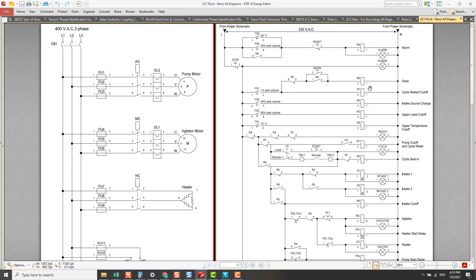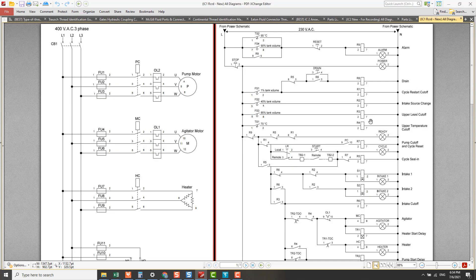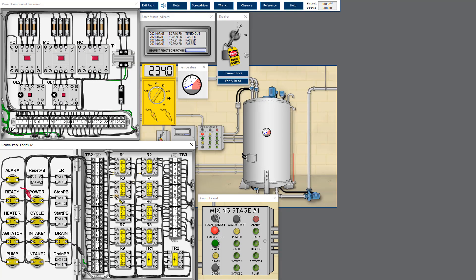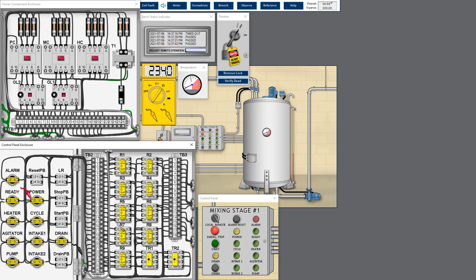Now I continue to check R8, R3, R4, and R7. Checking before the load at R8-7, R3-7 and R3-2, R4-7 and R4-2 — resistance remains the same, no earth fault before the load or at the load. Then R7-7 and R7-2 — still the same.